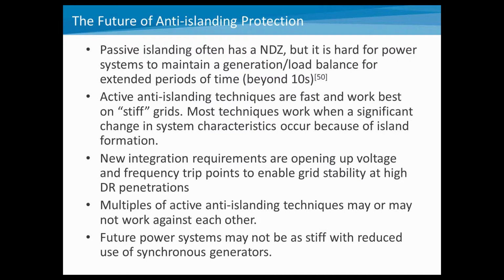One of the things that we don't have a lot of work on is multiple active anti-islanding techniques. They may work with each other, they may work against each other. It kind of depends on which techniques they're using. And as we look to future power systems, if we lose a lot of synchronous generation, they may not be as stiff. So we may be forced in general to allow distributed resources to operate in a bit wider range of voltage and frequency settings.